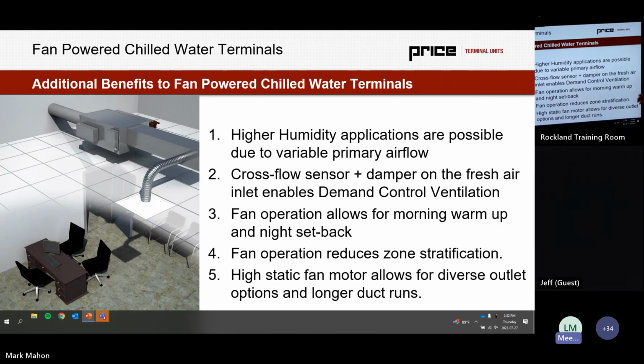So one is the capability of some higher humidity applications, due to the fact that we have high variability to the primary airflow rate. An application comes to mind in particular, which was a high-performance school that had a small lobby area, but it did have air infiltration. And rather than needing to get a fan coil that could do latent cooling, what they actually looked at doing instead was they kind of sized what would be their typical design day based off of ventilation rates for the space. And then they sized a higher ventilation rate for dehumidification purposes. And if they needed, they could elevate just that one zone up to dehumidify the space.